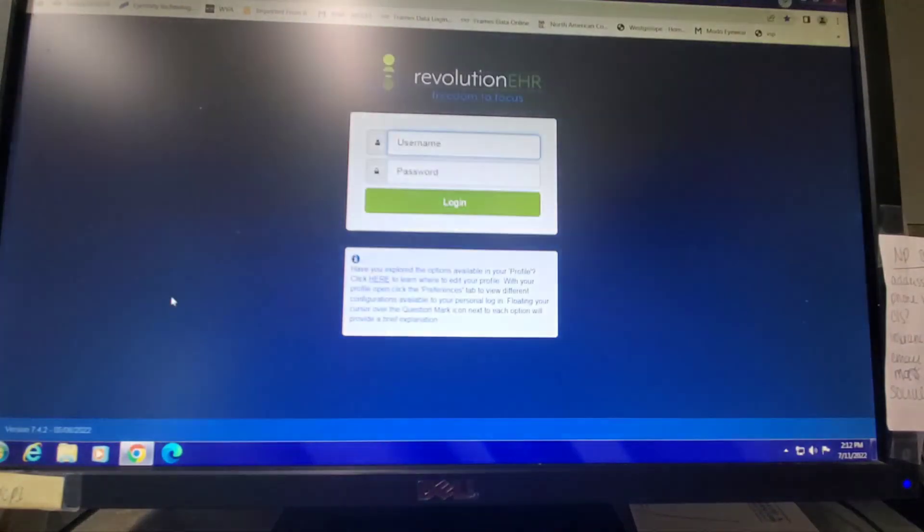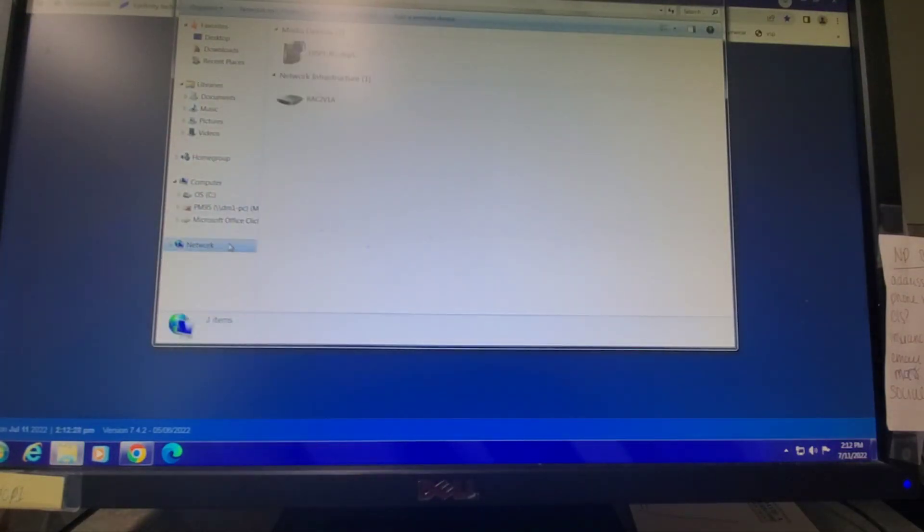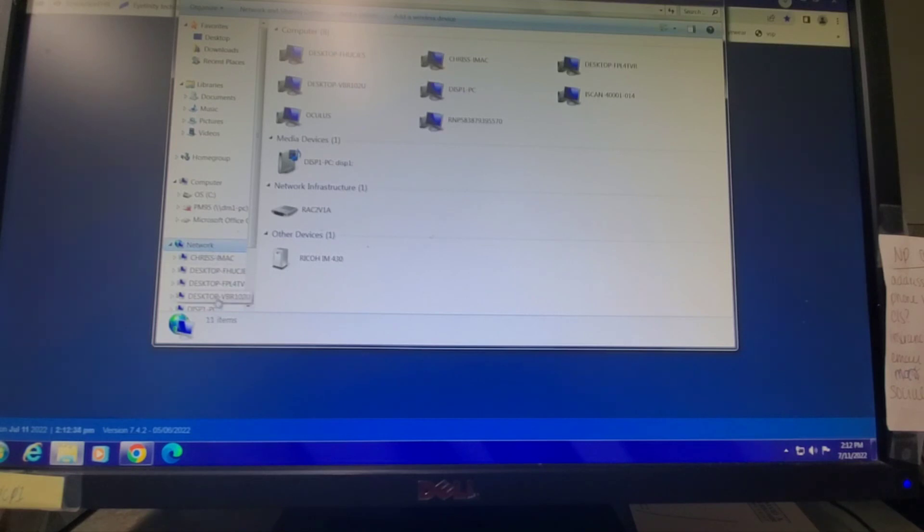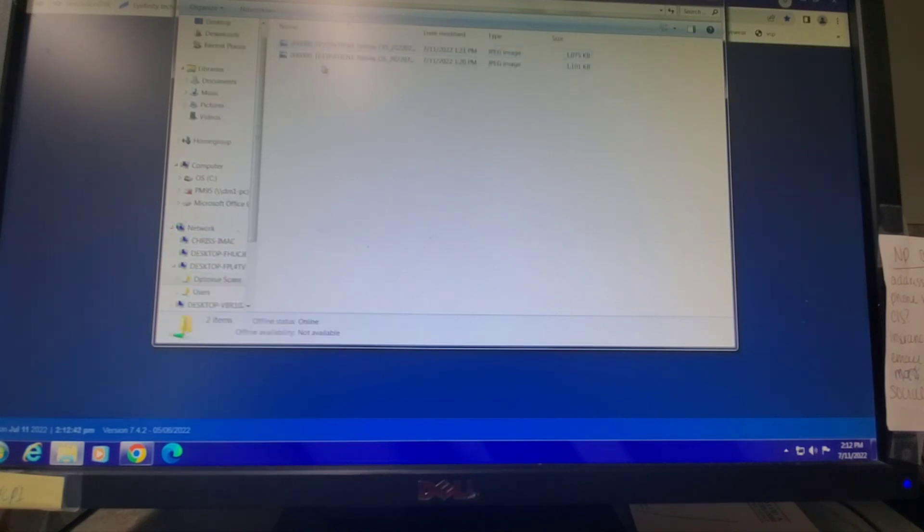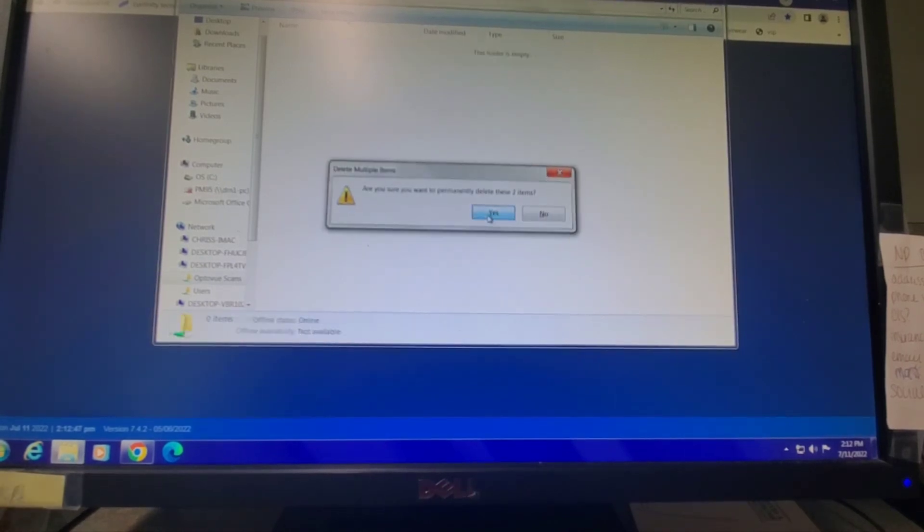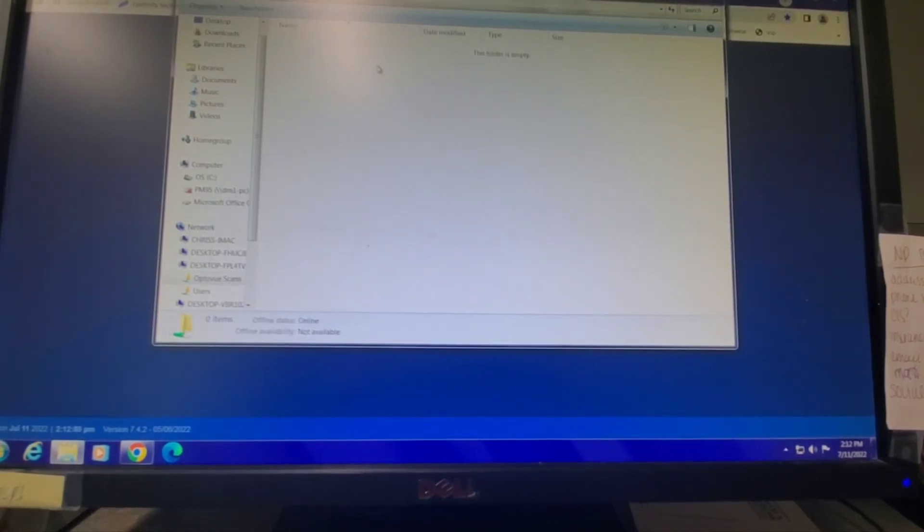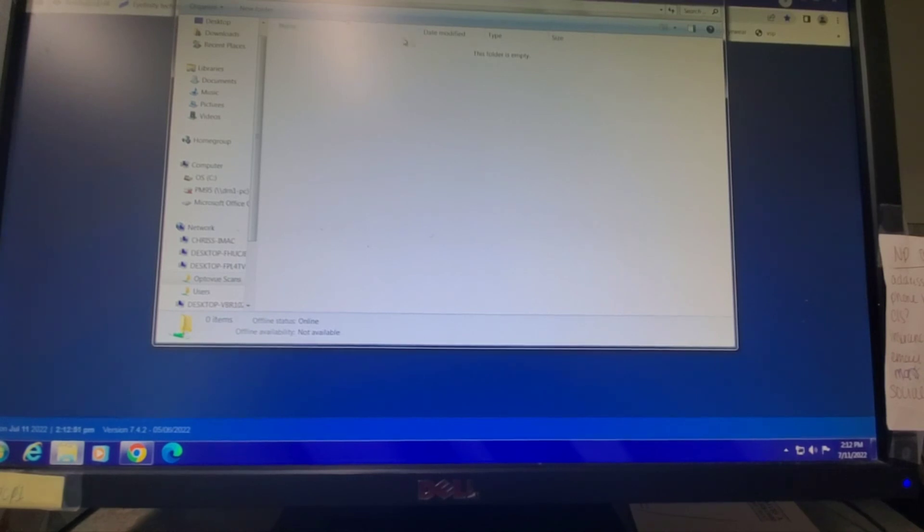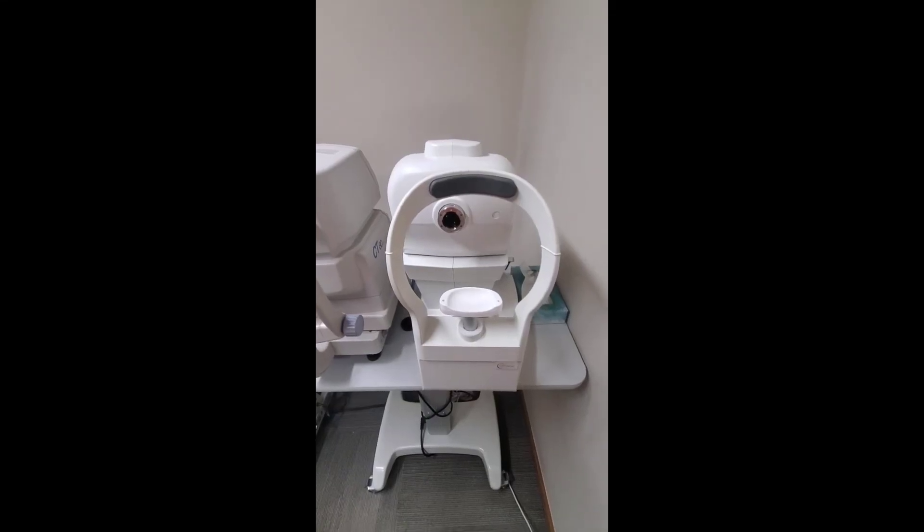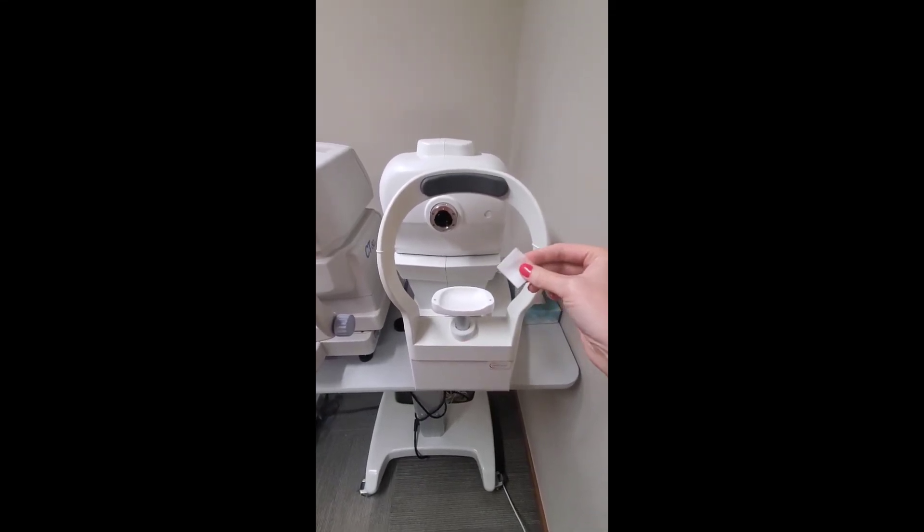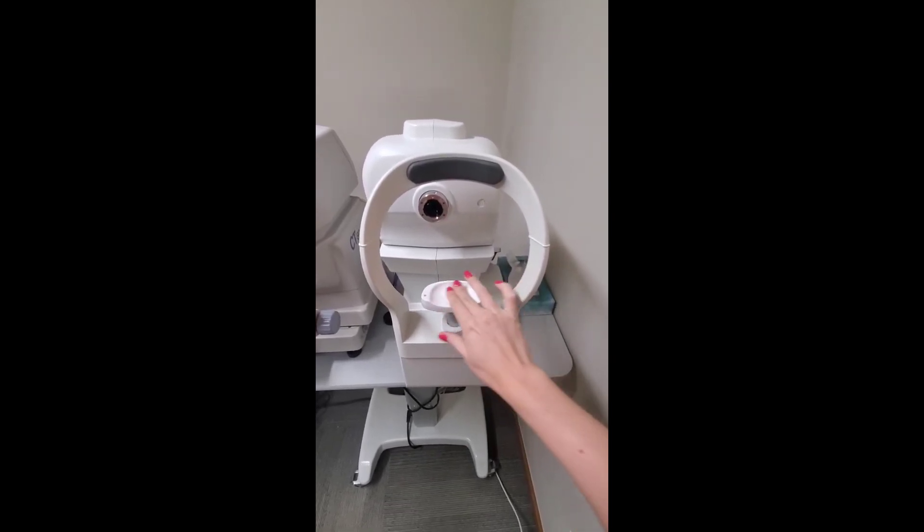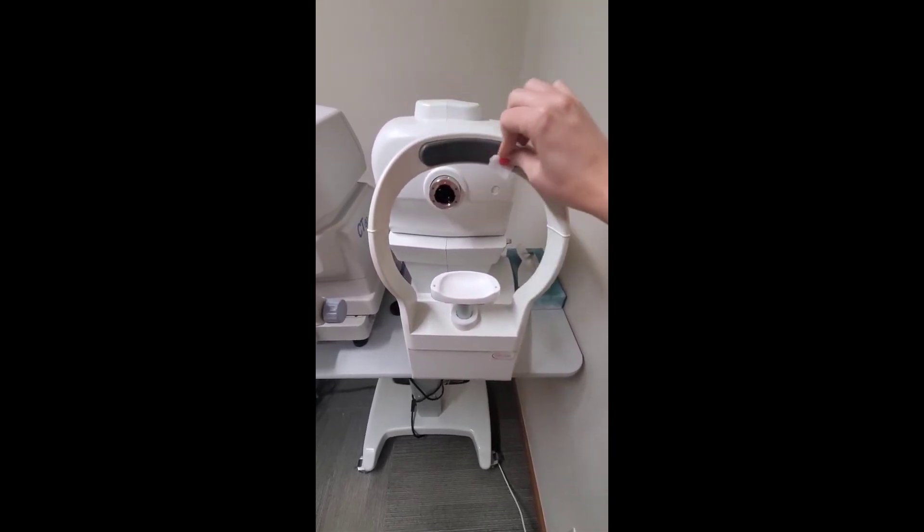Now we do want to go back in and delete the photos from the folder just so that we don't get too many cluttered in there. I went to network. I'm going to find the FPL4TVR folder, OptiView scans, and then I can delete both of those. That way next time when another patient's photos are exported, we don't have a lot that we have to search through. We just keep this folder empty to make it easy. When you're done using the machine, we'll have to clean it off. You'll take an alcohol wipe and wipe the chin area and the forehead rest.